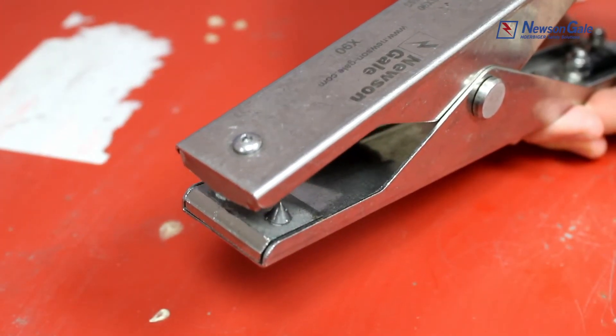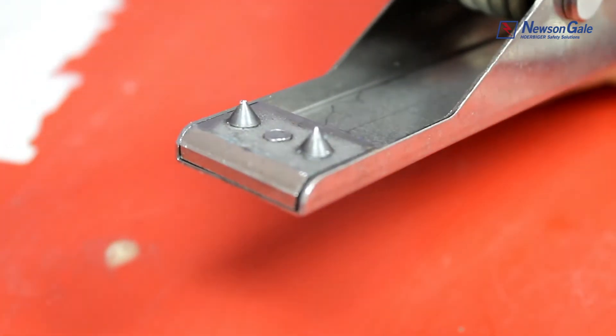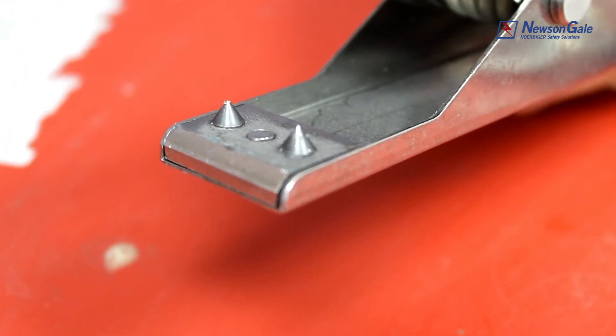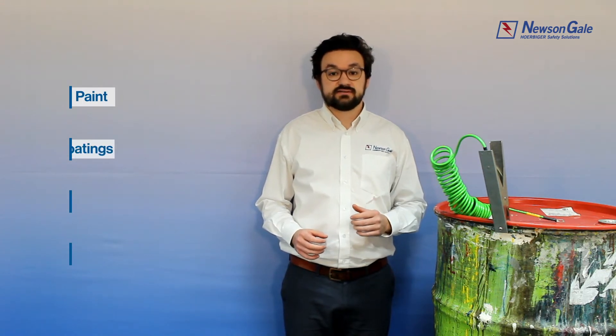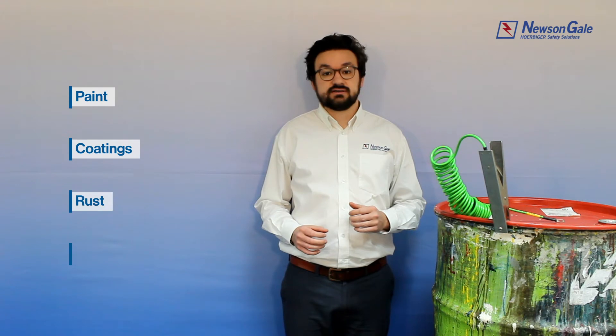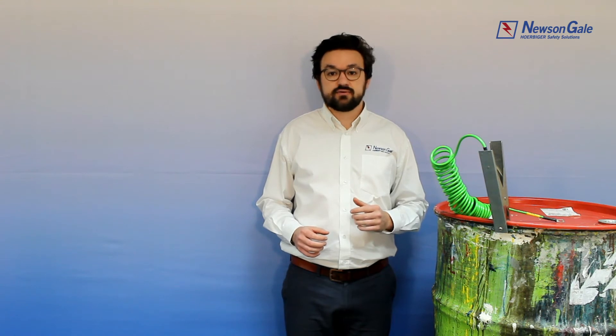In an effort to control this risk, Newson Gale's clamp tips are equipped with one of the hardest wearing materials used in industry today. Tungsten carbide teeth are designed to penetrate paint, coatings, rust and product deposits. Static grounding clamps must be capable of breaking through these inhibitors to ensure a good low resistance electrical connection from the process equipment to ground.